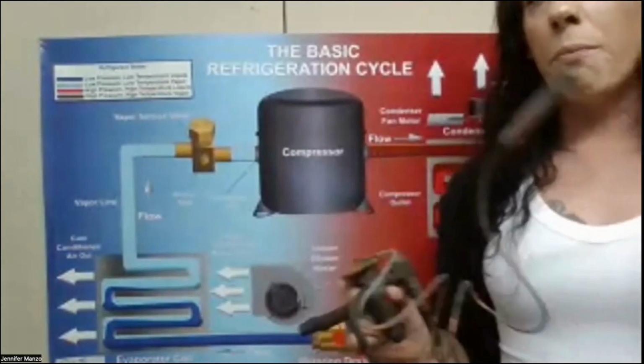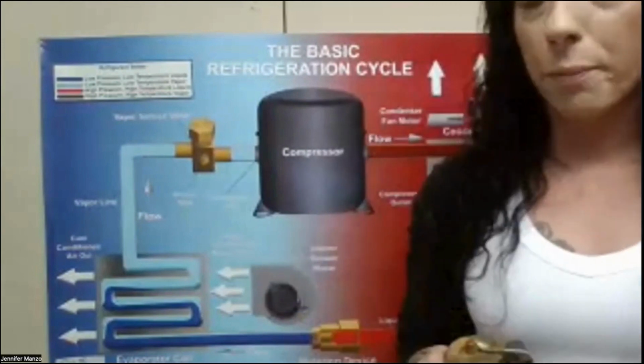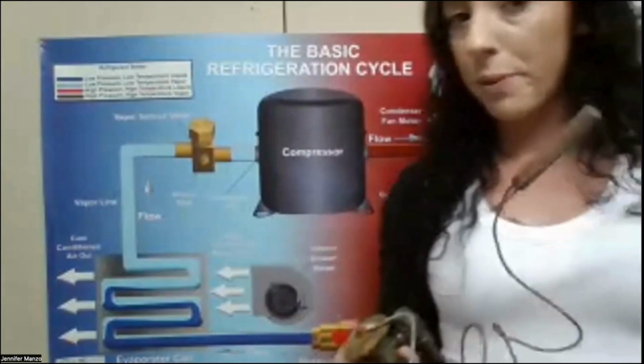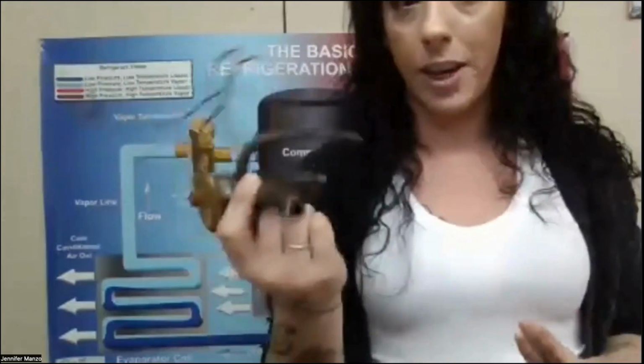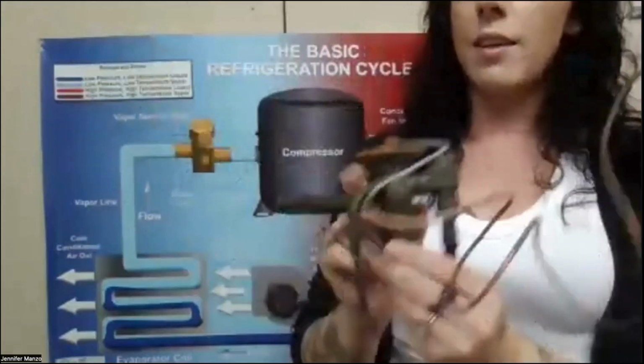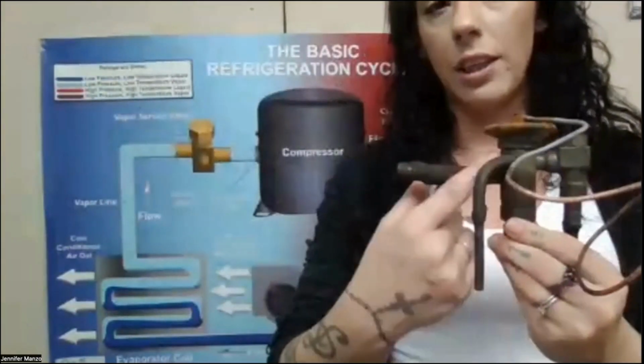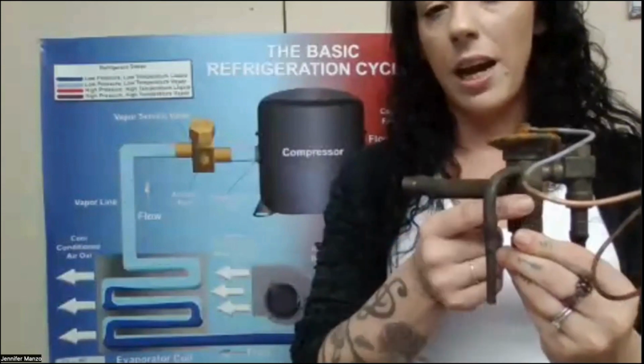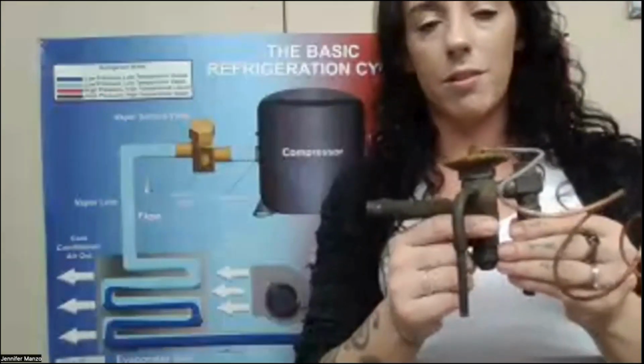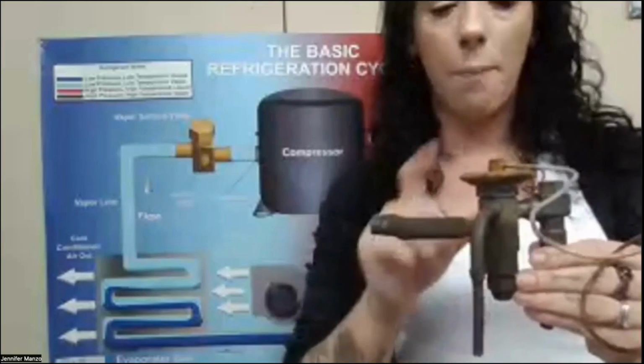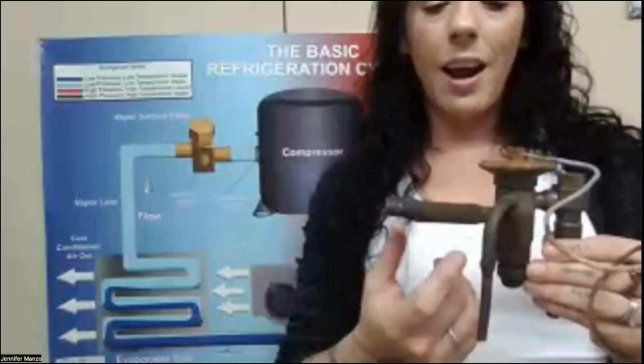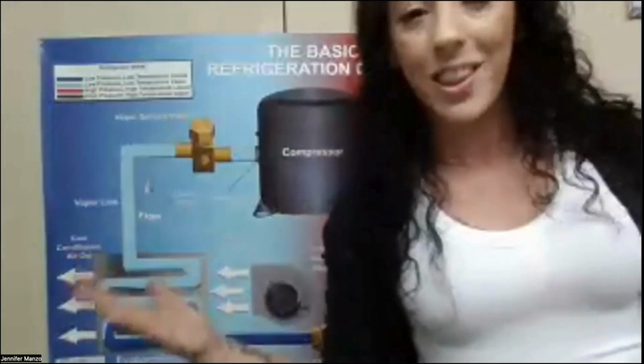If you're getting more vapor than you need, then your load probably isn't high enough. And if you're getting less vapor than you need, you probably got a restriction in your TXV, which happens all the time. Because inside here, there's a valve that goes up and down to let the refrigerant out. And sometimes it gets crusty with sediment, or all kinds of things can happen. This power head can stop working, and then you've got to replace the TXV. And there's a joke in HVAC that it's always the TXV, no matter what.